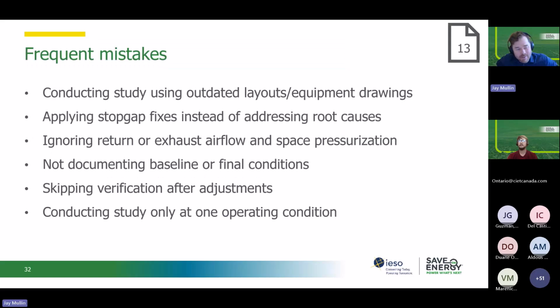Some common mistakes that happen in these studies: balancing to outdated layouts or equipment. You want to verify all as-built conditions and confirm current equipment configuration before taking any measurements. Another common issue is applying stopgap fixes instead of addressing root causes, like wedging dampers open instead of figuring out why they aren't operating correctly. So make sure you measure the airflow first and identify the root cause of the imbalance, and then make adjustments based on the data, and not just, it's negative pressure, let's jam a damper open to address that.